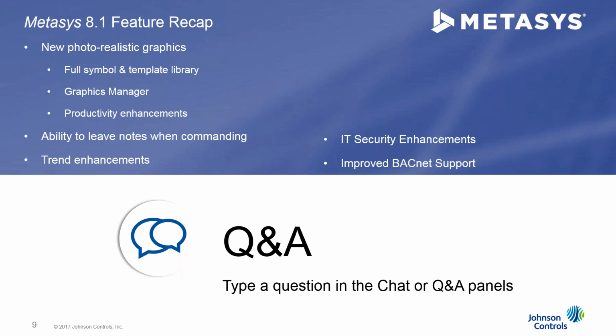Okay, great, thank you. Can you confirm, do you still need to access Metasys through the launcher, or is it accessed through an IP address? The Metasys user interface, the web interface that we just showed, is accessed through one of our web browsers such as Google Chrome, Safari, Internet Explorer, that's installed on the machine. At this point, most of the operators on site can use the Metasys web interface. There is some enhanced functionality for advanced control specialists such as system administrators that you can get to in our site management portal. If that user needs to get at something more advanced or a network configuration in the system, they would use the launcher to get into the site management portal. But that only really needs to be installed on a couple of machines or technician laptops in the facility.